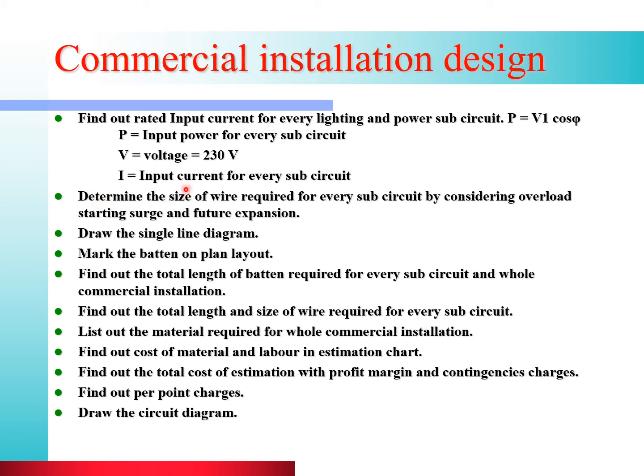Then after calculating the input current, you have to determine the size of wire required for every subcircuit by considering the overload, starting surge and the future expansion. Then by selecting the size, draw the single line diagram of the lighting circuit and the power subcircuit. Mark the batten on the plan layout.